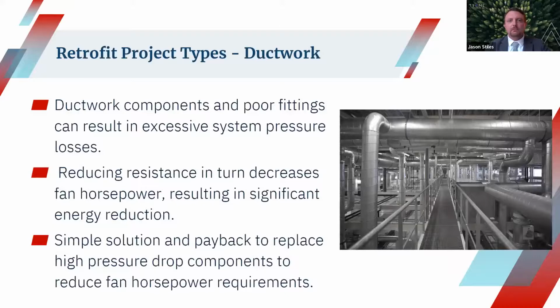Moving to the next slide, we look at some low-hanging fruit—projects don't all have to be major. We can see just from looking at the ductwork: older buildings typically have poorly configured, chopped-up ductwork from retrofits over time or construction projects, causing pressure loss from system effect and increased energy consumption.